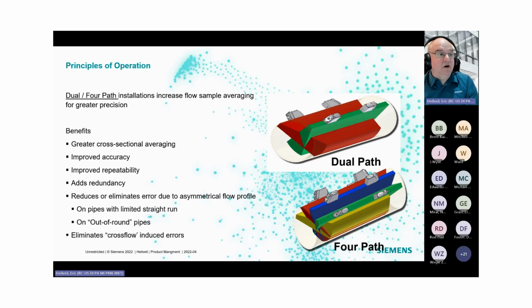The transmitters are set up to be, when you buy them, either single path, dual path, or 4-path. So if you currently have a dual path system, it would be just a matter of getting an additional transmitter and the additional hardware to create the extra paths. So if you have a single path or a dual path system, you can upgrade it, but you'd have to change the transmitter to do so.